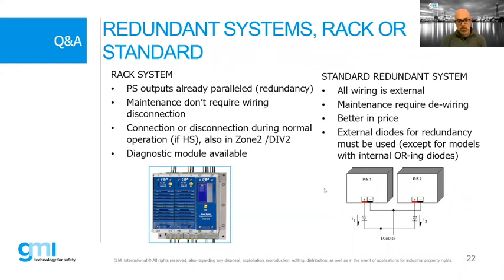In the standard redundant supply system, we need to connect externally, and maintenance requires rewiring the power supply. Again, in a standard redundant system we need to use an external diode for redundancy. Instead, in the rack system, the OR-ing diodes are already inside the system.